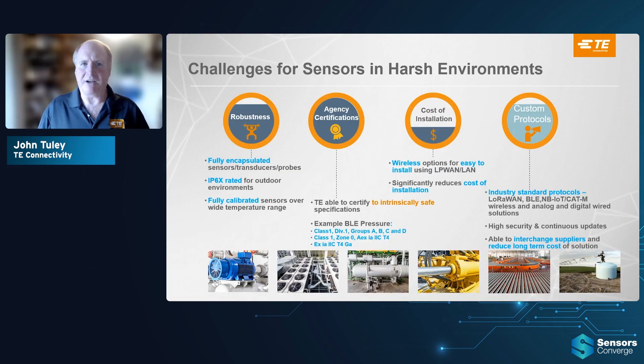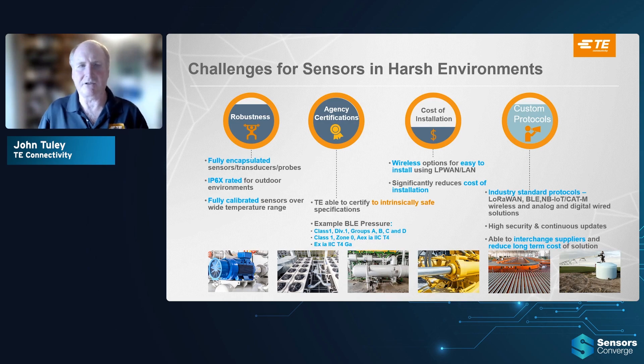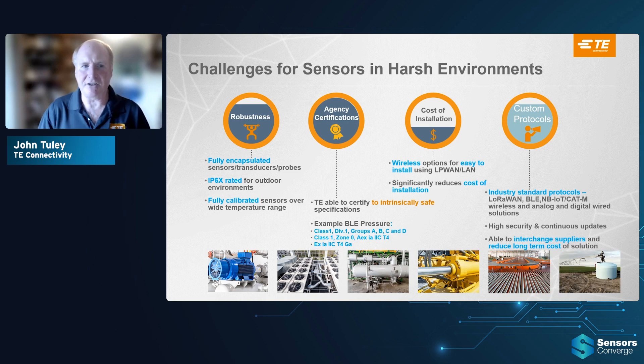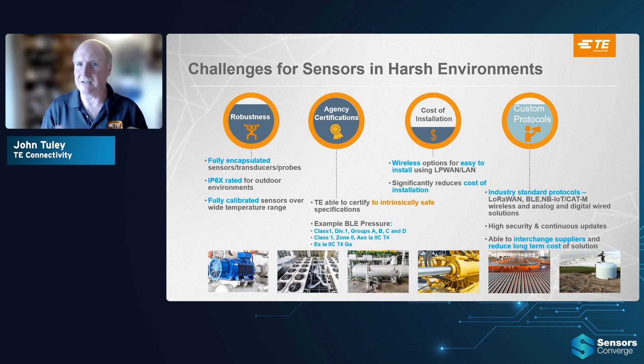When you're in hazardous environments, that presents another set of challenges, and this is what TE really excels at. 80% of our business is in harsh environments. It really comes down to robustness — fully encapsulated, IP67 and IP68 rated for washdowns, fully calibrated over wide temperature ranges. These sensors are out in the environment or on a factory floor with oils, so they have to last, be reliable, and continuously give good data, because that good data drives the analytics engines. These also require agency certifications such as ATEX, CSA, and Class 1 Div 1 — especially in oil and gas, chemicals, and gas manufacturing — to be intrinsically safe sensors. We have this in both wireless and wired portfolios to make sure they don't cause any safety issues.